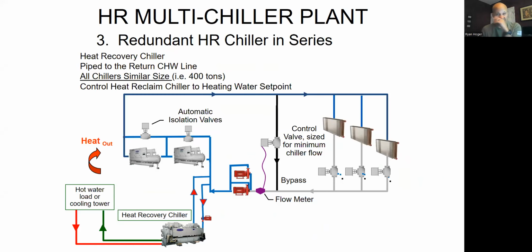All right, the third way is to have redundant chillers in series. So this one's going to control the hot water set point also. So the 2 hot water set point ones, I like those better. So he's going to say, hey, I want to make 125-degree water, or whatever you designed it for. Make me that water. I'm going to have a temperature sensor in the pipe to do that. And this guy's going to run to maintain that water to give heat to whoever over here wants this amount of heat, right?